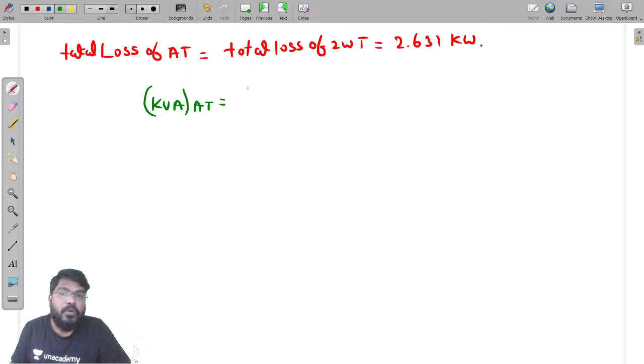Now what about the kVA rating? The kVA rating is not the same, it is different. The kVA rating of the auto transformer is equal to 1 by (1 minus K) times the kVA rating of the two winding transformer. K we have already calculated: K is equal to 2 by 3, into 50 kVA. So 1 by (1 minus 2 by 3) means 3 times 50, which is equal to 150 kVA. All of you clear now?